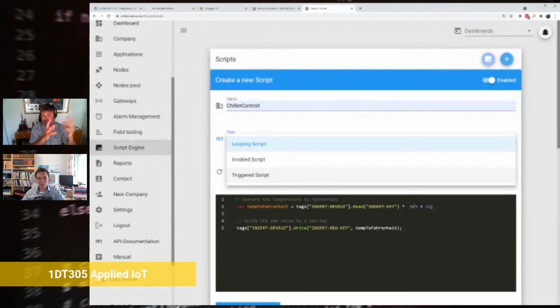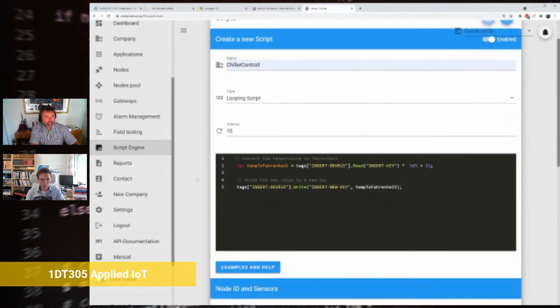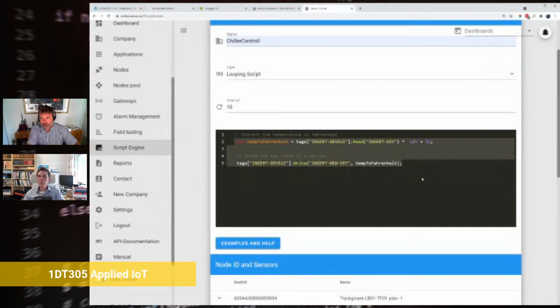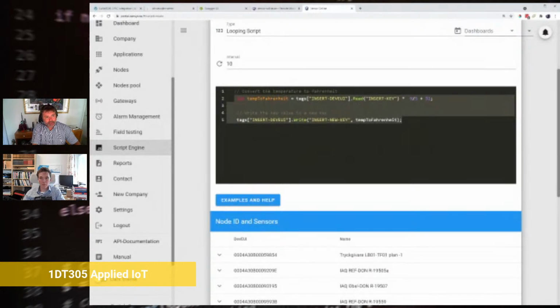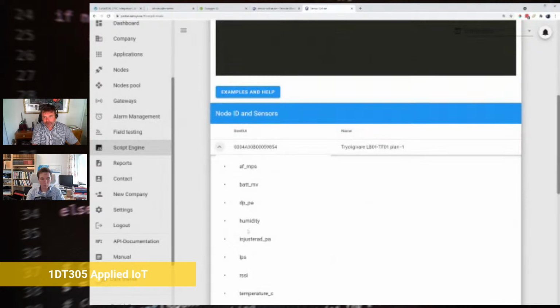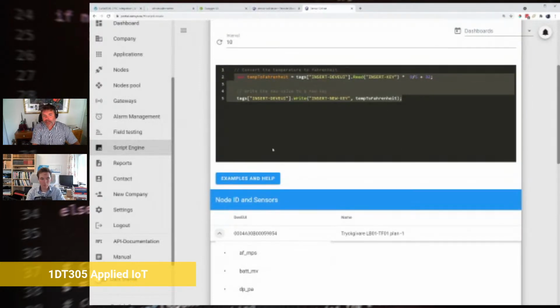So for instance, if you want to do an average, once those sensors arrive at the server we will do a new average calculation. It's 100% JavaScript syntax, but we've built in a few extra features. So if a sensor made in the US sends temperature in Fahrenheit, but you live in Sweden and want Celsius, you need to convert that. You write a variable tempFahrenheit equals tags, choose the sensor device, and read the key - cut that and paste it in here. Then you can write this sensor data back to the database, meaning you've created new calculated sensor data based on incoming sensor data or events.